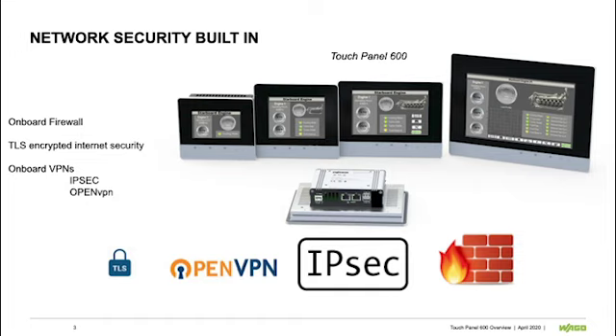The other feature on the device is TLS, or Transport Layer Security, for encrypted HTTP communications. This feature can be enabled to help with securing communication between servers and web browsers. And the TouchPanel 600 has features for VPN capabilities, that is, a virtual private network that is used to protect data online. The devices support both IPsec and OpenVPN platforms. The user can enable one or the other in the HMI's web-based management.